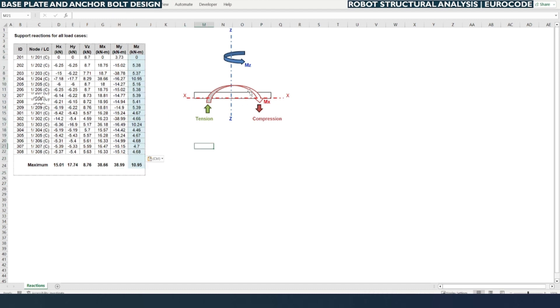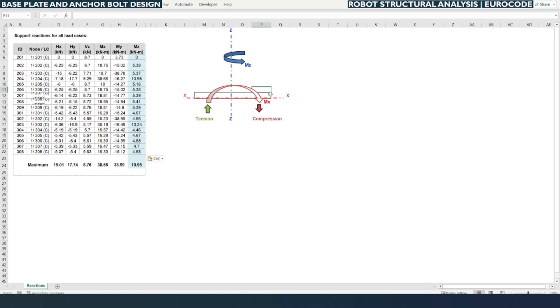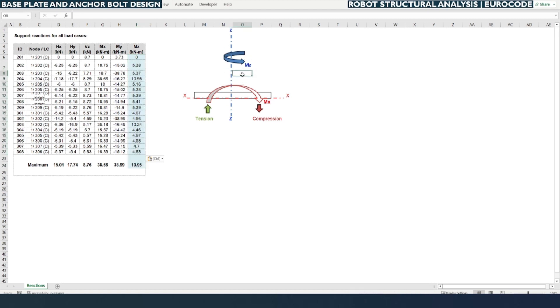We can ignore Mz because, as shown in the picture, if the base plate is like this, the moment causing rotation about the Z axis (vertical axis) will not make any changes in the base plate or anchor bolt design. But for moments in the X and Y direction, the tail part of the moment arrow will cause tension (uplift) and the head will cause compression. Mz is ignored as it is only vertical rotation.